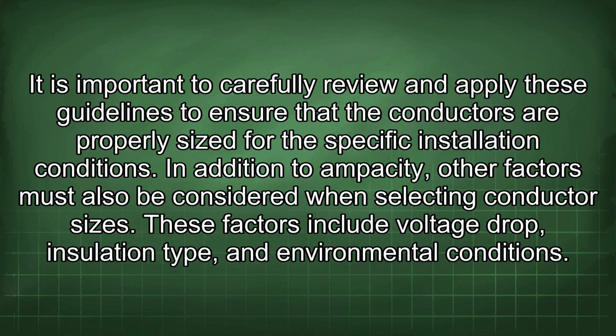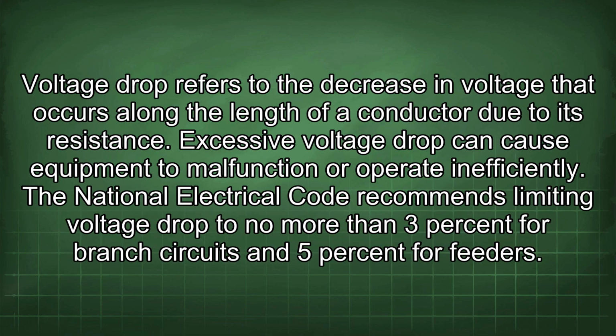In addition to ampacity, other factors must also be considered when selecting conductor sizes. These factors include voltage drop, insulation type, and environmental conditions. Voltage drop refers to the decrease in voltage that occurs along the length of a conductor due to its resistance. Excessive voltage drop can cause equipment to malfunction or operate inefficiently.